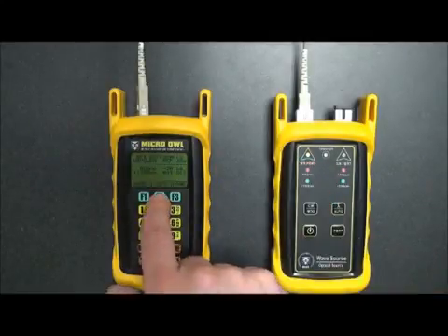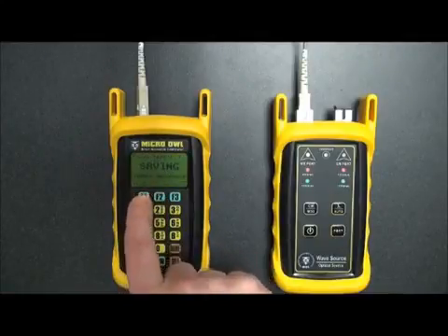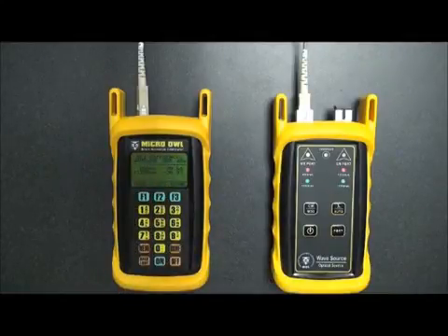And we just press F2 to begin the set reference procedure. And we'll press F1 a couple times to confirm. And as you can see, now our 1300 reference is minus 20.33. This is still okay. So what we've done is we've set our references, and we are actually done setting our references, inputting all of our link information.